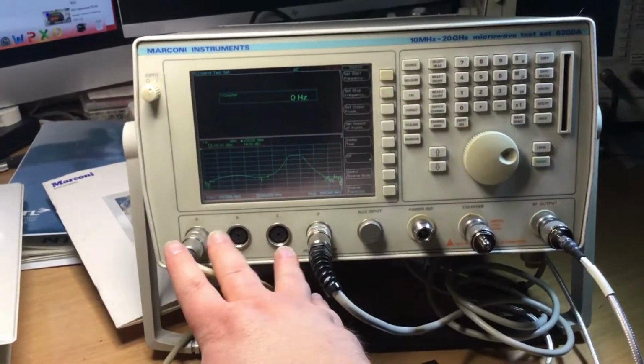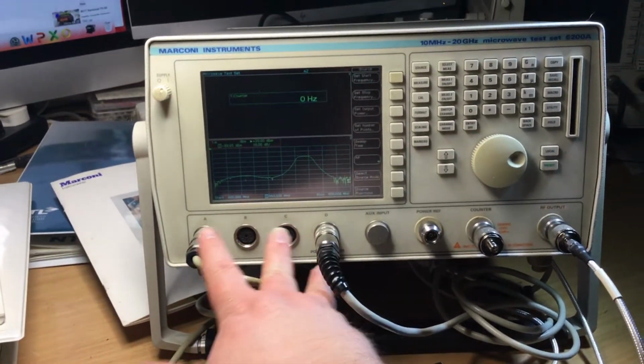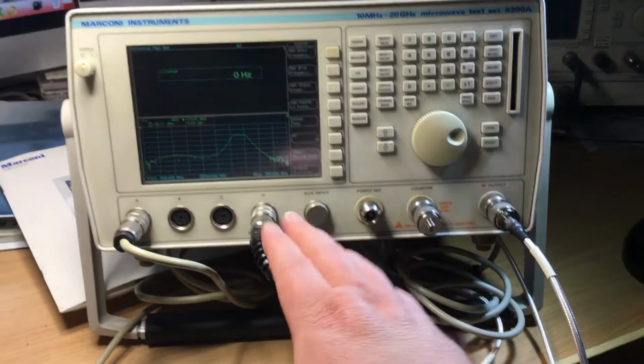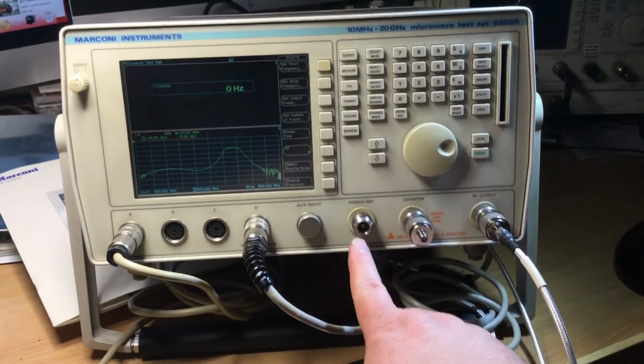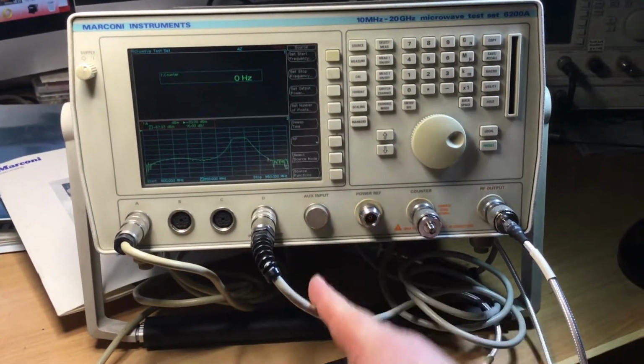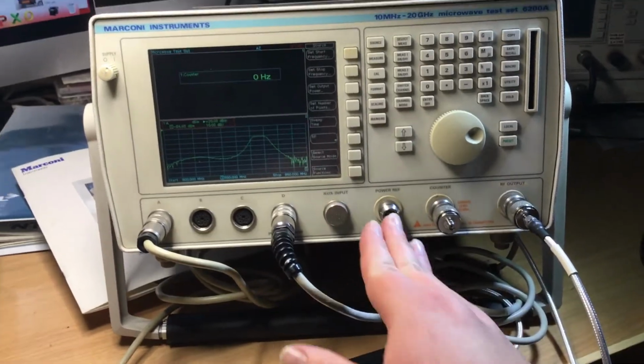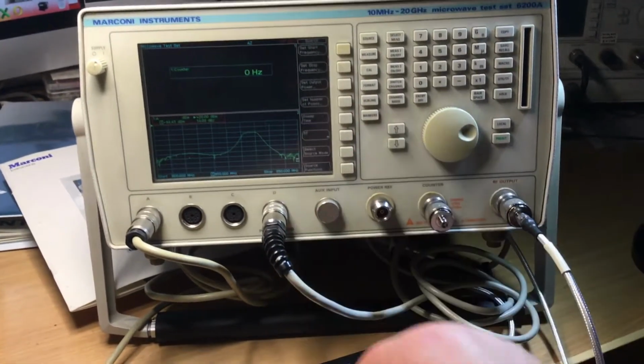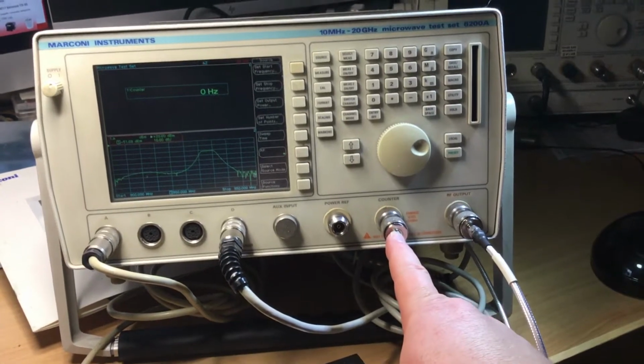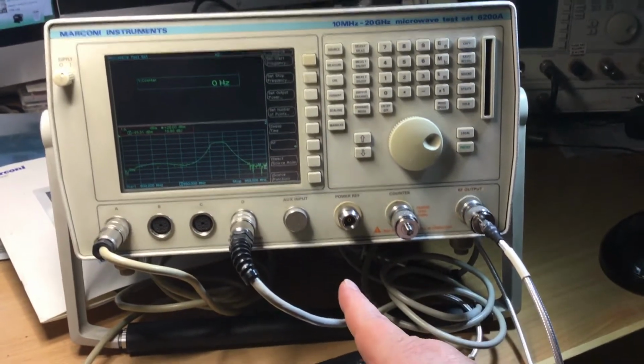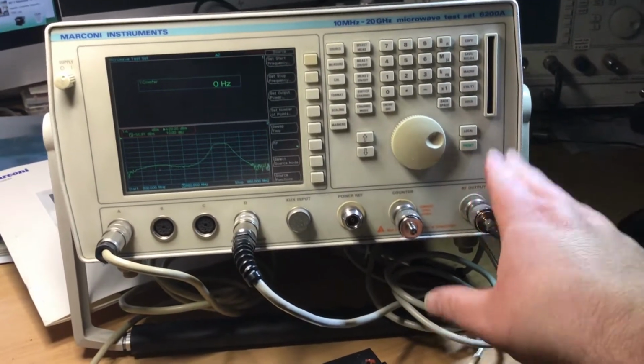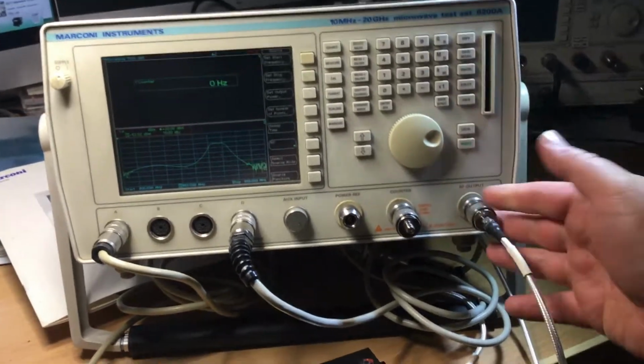So that's what we've got. We've got the inputs here for the sensors to connect in, the accessories port. That's the calibrator output where we calibrate sensors - we connect them on there and run calibrate mode. This is a frequency counter input, which I'll demonstrate shortly. And that's the RF gen output, whether it's a single frequency or a swept frequency.